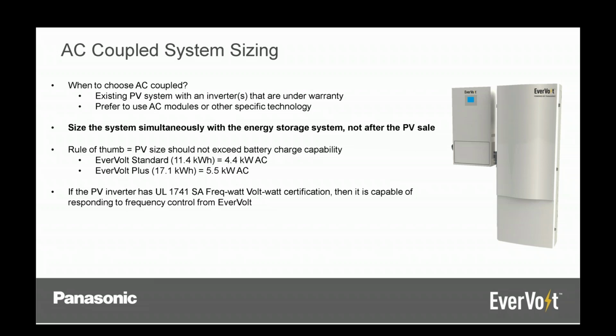Hopefully this makes basic sense where our batteries are concerned. For EverVolt Standard, they're rated at 4.4 kilowatts of AC power. The EverVolt Plus, 5.5 kilowatts of AC. So in the very basic rule of thumb, you don't want to have more than that power available from PV, right? Otherwise, during a grid outage, that extra power is going to trip something. Now, that's the basic guideline.